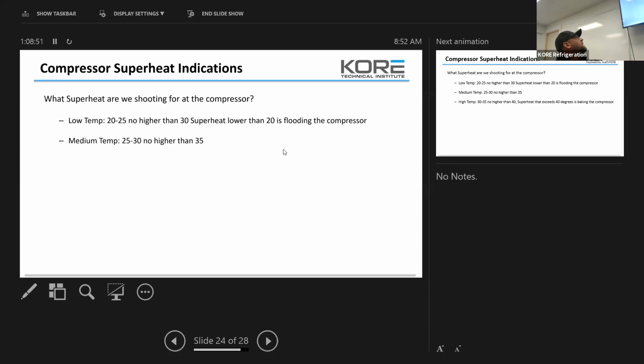Medium temp, this is coolers. Medium temp, 20 to 30, no higher than 35. So this is optimal running. Sometimes you'll see a little bit more, depending on conditions, depending on piping. But again, we've got to have something to shoot for, so this is what I want us to shoot for. So high temp, 30 to 35, no higher than 40.